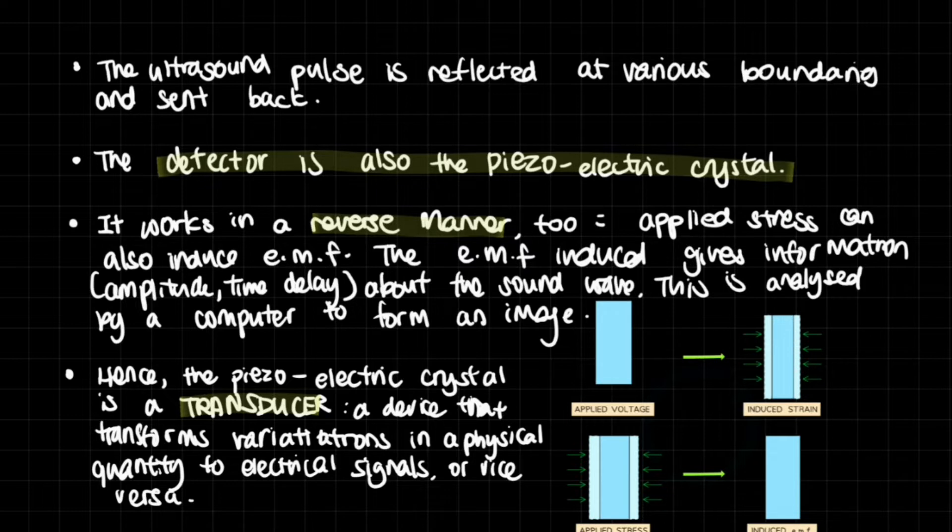If there is an induced EMF on the crystal, it's going to change shape. But if the crystal is meant to change shape because of different pressures, the crystal is also going to induce its own EMF. The EMF induced gives information about the sound waves - amplitude, intensity, and time delay. This is analyzed by a computer to form an image. The piezoelectric crystal is a transducer, a device that transforms variations in a physical quantity to electrical signals or vice versa.